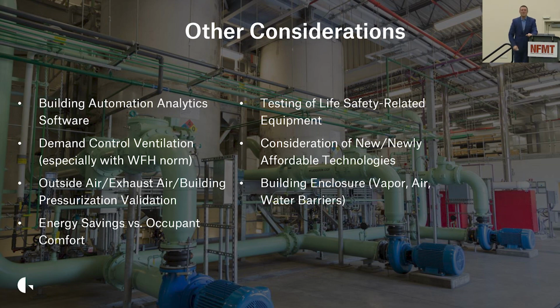Energy savings versus occupant comfort - you can run into a case where your facility staff is so exuberant to save money that they end up compromising occupant comfort by limiting the conditioning efforts of the HVAC system. So it's something to consider if you really want to save money - you cannot let people adjust the thermostat below 75. I've seen that in a building. Instead of changing lights, you just turn them all off. Yeah, everybody's angry and you're saving a lot of money.